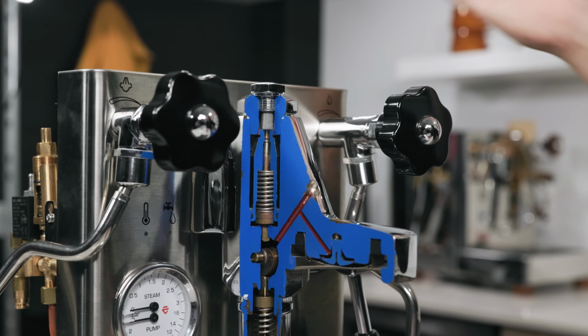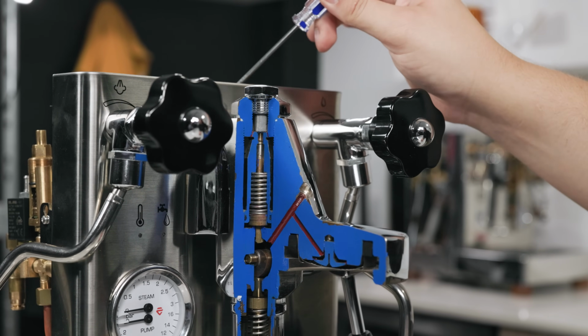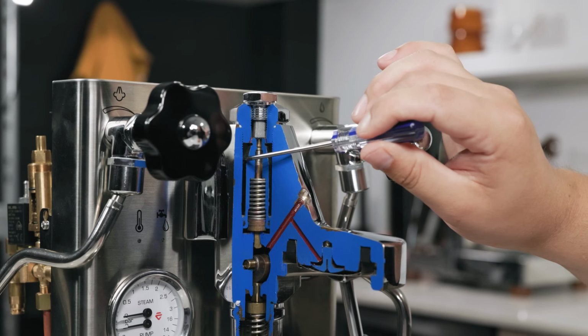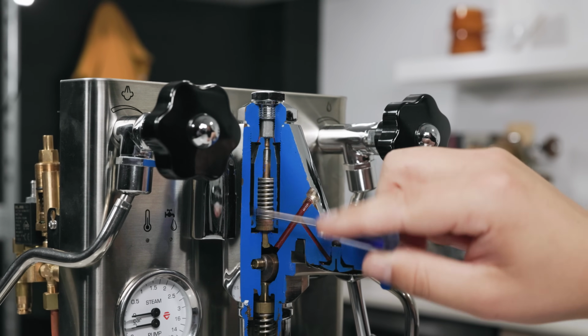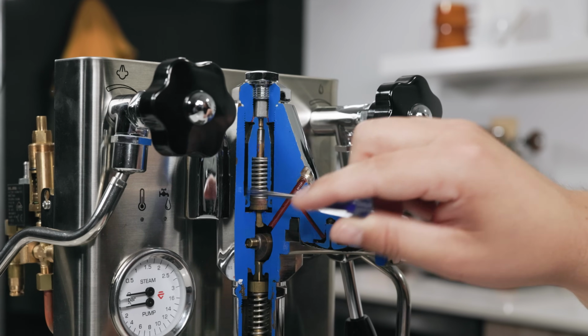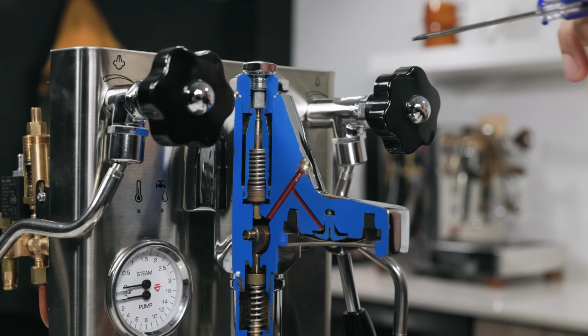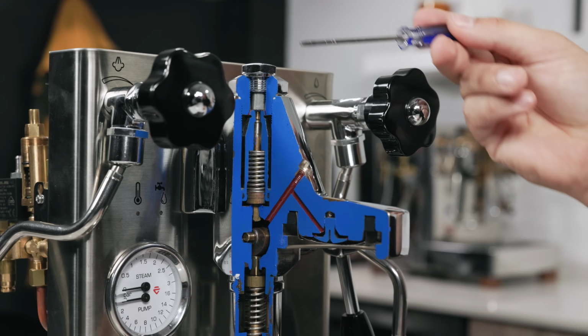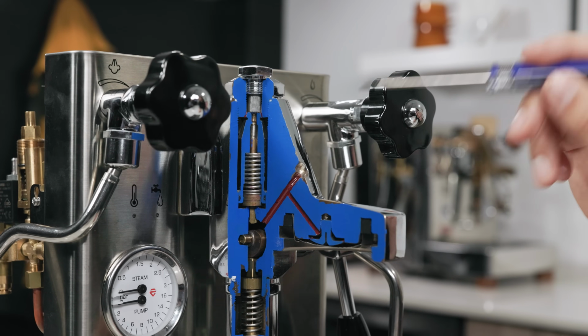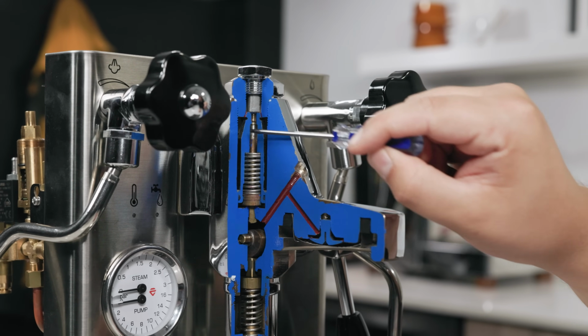So it's coming out without the pump being turned on. Very slowly, water is sputtering into here. That's very hot. It fills this chamber, and then there's a hole at the bottom of the chamber, and that's where the exit tube is to re-enter the boiler. So we have a constant thermosiphon loop that's going on inside of this chamber surrounding this.